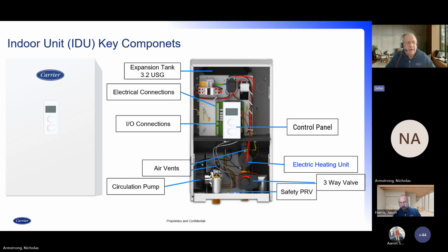Now, with hydronic systems, air is probably the one largest obstacle to providing consistent heat. And having an air vent built into the indoor unit is a really handy thing to have. Now, we certainly wouldn't say you only need one air vent. There's nothing wrong with having more than one air vent in a system, and we always ask that you put an air vent at the highest point of the system to allow the removal of air from the system. There's a circulation pump built into the unit, a safety PRV, which is set for 30 psig. There's a three-way valve also built in with a manual override. The three-way valve acts as the ability to divert the flow through the heating or cooling or into domestic hot water production. You have electric heating backup inside this unit. For the small sizes, there's two coils. For the large size, there's three coils.